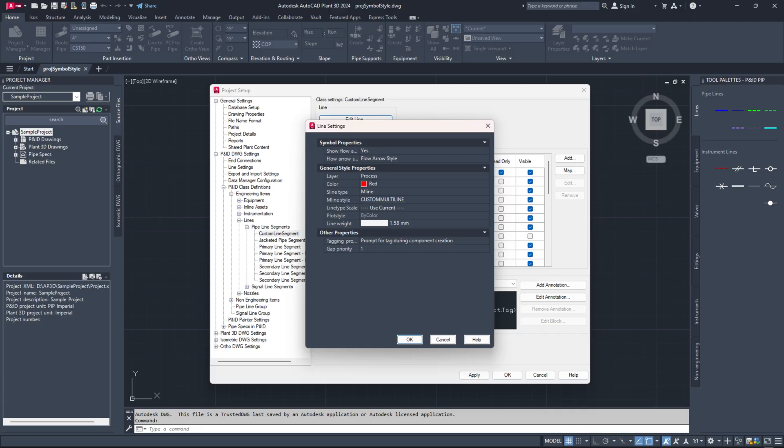To show process lines as a double line in the P and ID for steam tracing, electric tracing or jacketed lines, then set this line type to M line and choose the new M line style from the drop down in the line settings dialog.